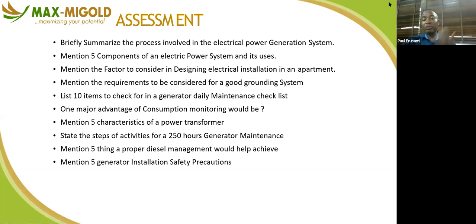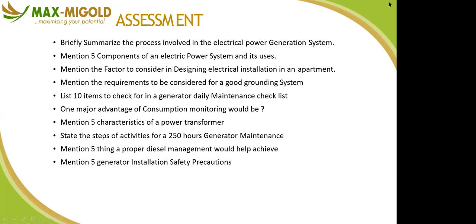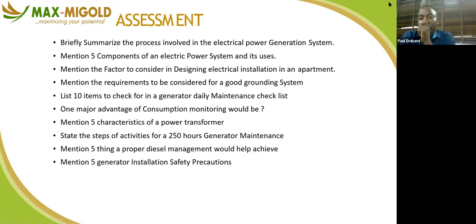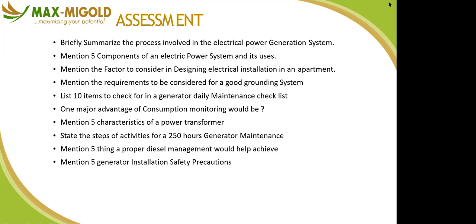Yes, okay. As for generator consumption, the lady mentioned that our peak period is 200 kilowatts and our off peak is 90 kilowatts. But what I understand, I don't know if I'm right or wrong, I know that a 100 kVA generator produces 80 kilowatts.